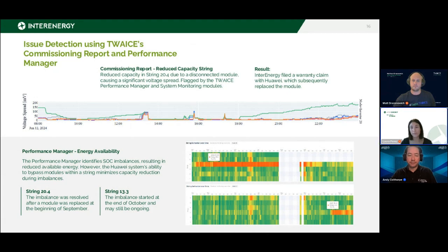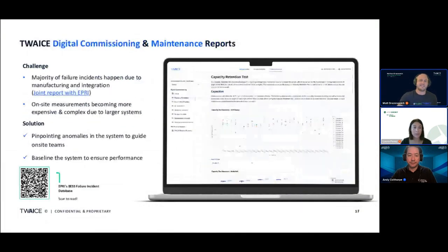Matt can give us more details. Just really quickly, we offer digital commissioning as a service, but really where this becomes important is uncovering a lot of issues that wouldn't normally be seen in raw data. So we track a number of KPIs around capacity, round trip efficiency, and DC resistance. We've talked about this study in other webinars, but EPRI has found that most equipment issues we see are introduced during commissioning, so it's important to have a closer look at the data at this time.